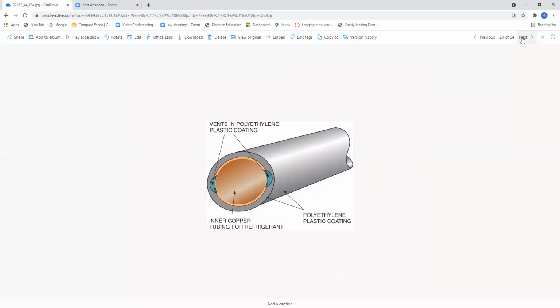Now, what goes on with this piping here? Okay, basically in this type of piping, which is found on page 1345, two small vents or grooves allow the pipe to act as a vented double wall heat exchanger. The inner part of this is copper tubing for refrigerant. And then of course the polyethylene surrounds this copper tubing. And then we have the vents in this polyethylene plastic coating. And I believe this is to allow for expansion, contraction, remove moisture, that kind of thing. And this would be considered direct burial, if I'm not mistaken.